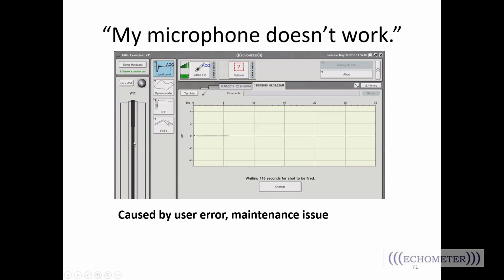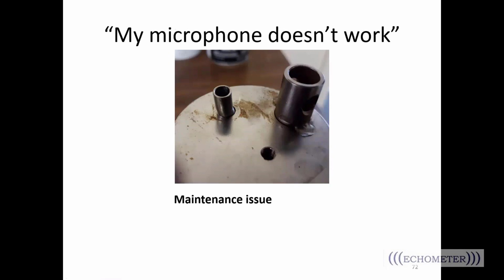All right, my microphone doesn't work. This can be caused by user error, or it could be a maintenance issue. You hit that take shot button and there's nothing. You just see this waiting for shot. All right, we're not seeing any register of the microphone. So here's one maintenance issue. Edwin, do you want to tell us what happened here?